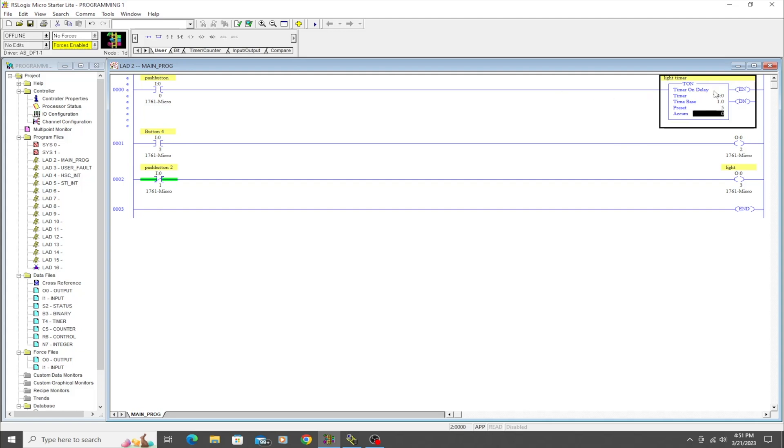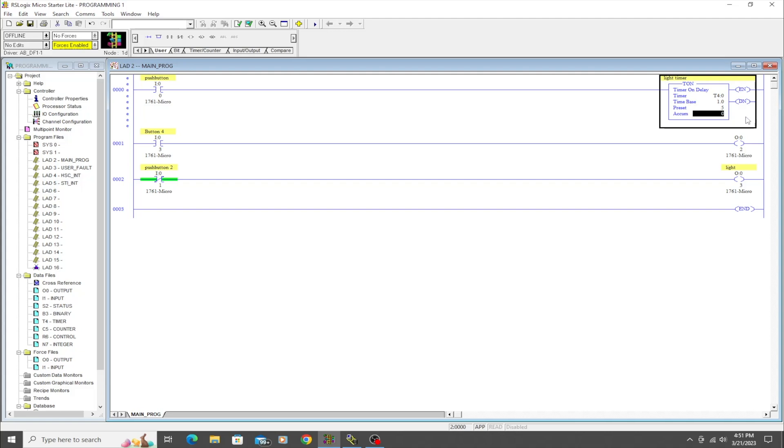If you hit enter, then it's going to take that. Accumulation is the amount of time that has accumulated on this timer. If we wanted to, we could put like a two right here and that would mean this timer already has two seconds accumulated on it, but we'll just leave that at zero. We'll hit enter and we're done with that instruction.